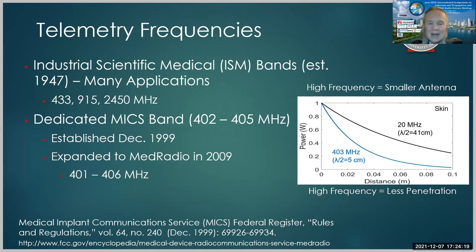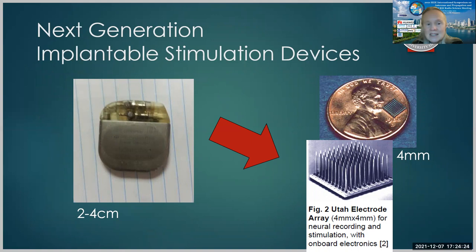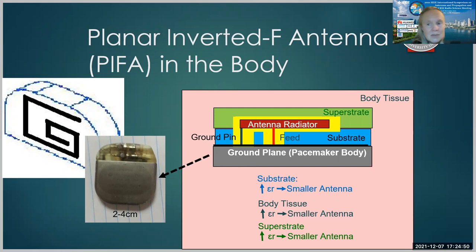So the challenge of next generation implantable stimulation devices are today's devices, the battery pack and the communication systems are generally two to four centimeters on a side. But in the next generation we'd like to be able to use very small devices, such as the Utah electrode array, a package of battery and electronics on top of that, and that device is only four millimeter on a side. So being able to shrink from a device that's two to four centimeters to four millimeters is a big challenge for antennas.